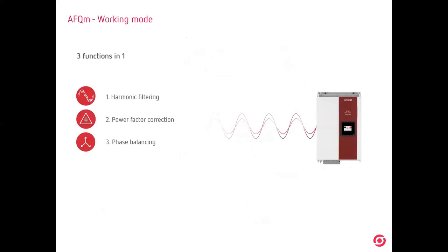And with a harmonic filter, with an active filter, we can work in three ways. We can filter the harmonics, eliminate, erase all the harmonics. If we have more power, we will be able to correct the power factor, okay? And then also we will be able to balance the phases. Balancing the phases means if you have an unbalanced installation, you will have current through the neutral cable, okay? This neutral cable can have problems, or the installation can have problems if you are creating this current through the neutral.